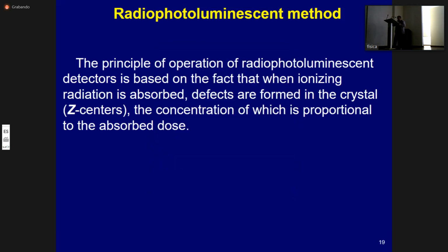The luminescence spectrum is due to the impurities initially incorporated into the phosphor. The intensity of the luminescence is proportional to the concentration of the created centers and consequently to the radiation dose. The intensity of radiophotoluminescence of the dosimeters, as a rule, initially increases linearly with increasing dose, then reaches a maximum and decreases with further increased dose.